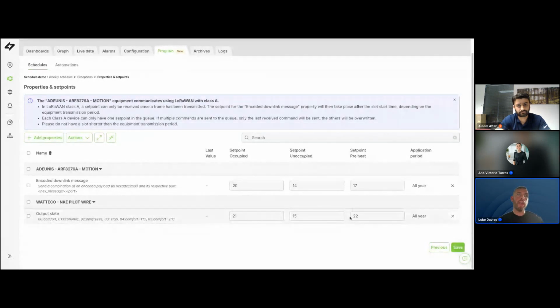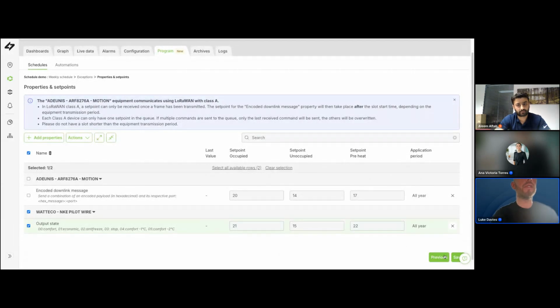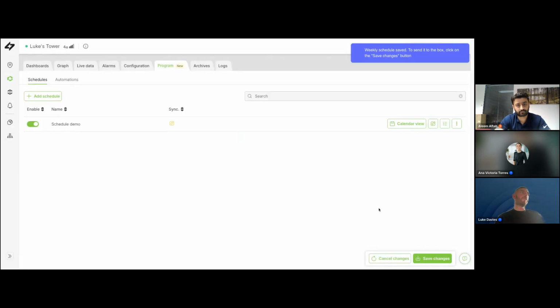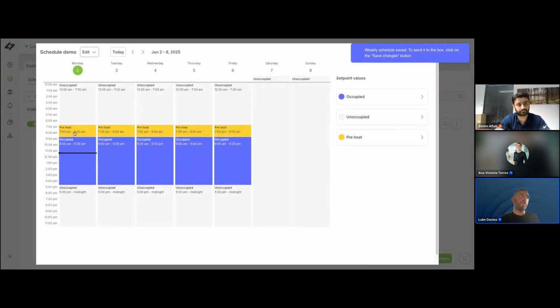We can preheat, so I showed you that you can preheat the school from 7 a.m. to 8 a.m. Obviously the preheat has to be higher than the original set point, and we set that at 22 degrees, and then once it's at set point, we drop that down to 20. So we just click that, save it to the box, and then the automation's there. So on your calendar view, your heating's turning on and off to this schedule.